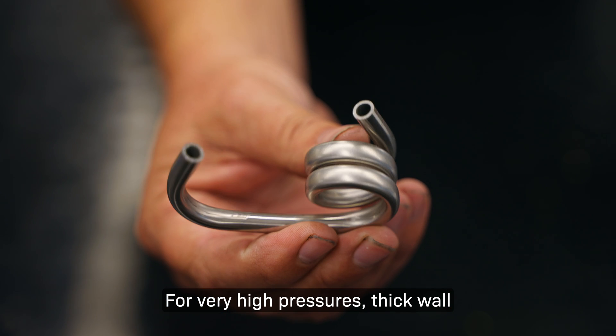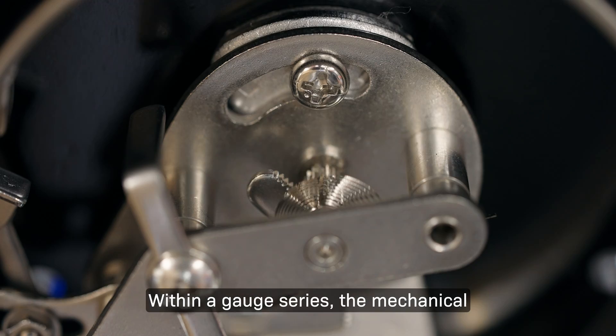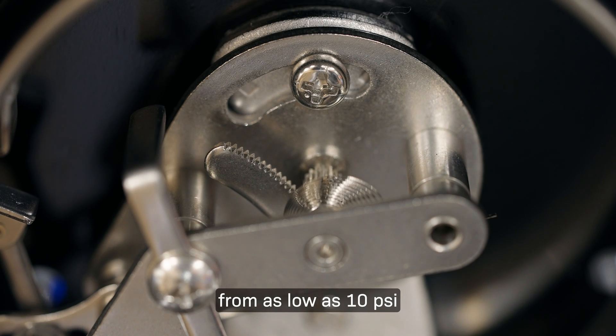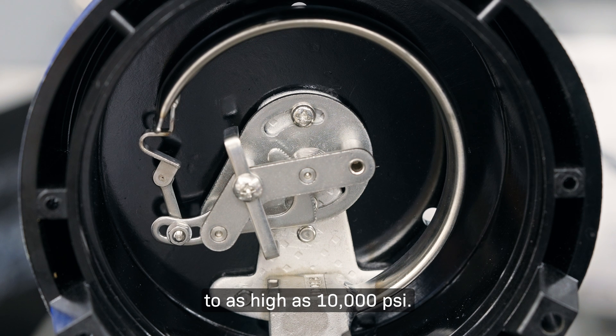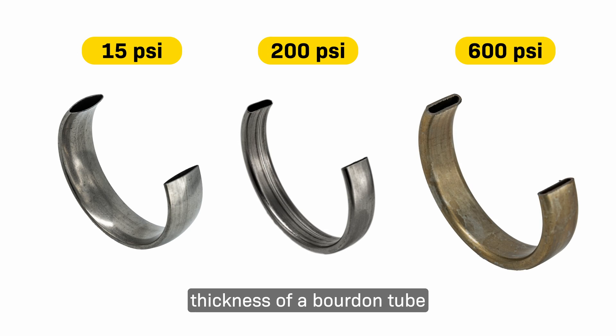For very high pressures, thick-walled tubing is used to create a helical Bourdon tube. Within a gauge series, the mechanical movement is the same from as low as 10 psi to as high as 10,000 psi. So it's the different size and wall thickness of a Bourdon tube that dictates the range of a gauge.